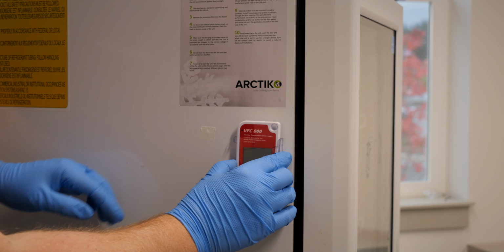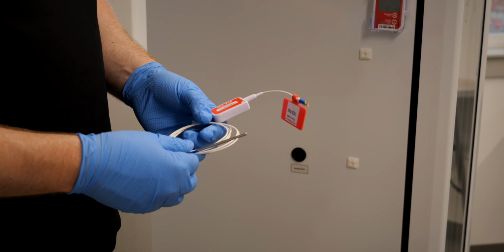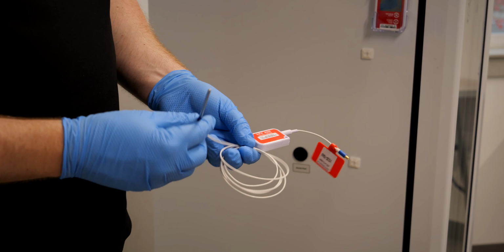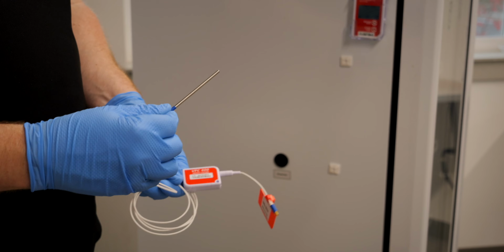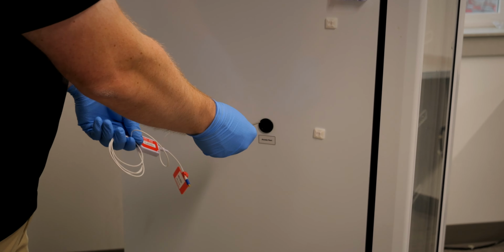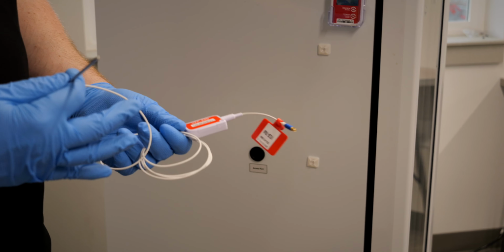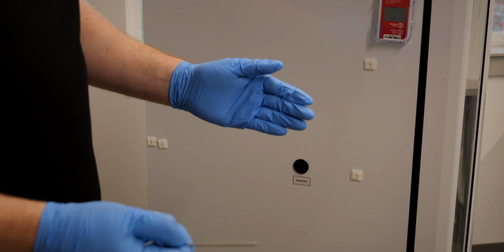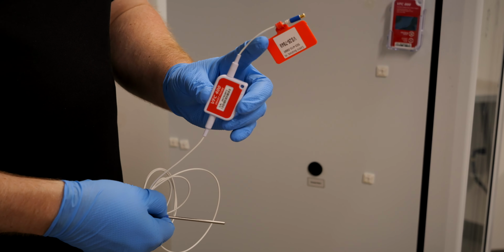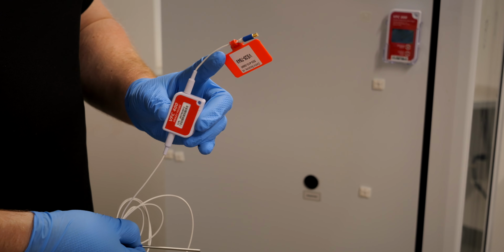Now that we have our data logger and the wall mount bracket placed on the refrigerator, it's time to install and route our probe cable. It is important to note that when installing our temperature probe, we always want to install it probe first into the interior cabinet of the refrigerator. So we're always installing our probe from the outside of the unit into the inside, because this will not fit through most fridge pass-throughs. So that's a tip to make it a little bit easier. That's also why during the unboxing, we took off the cap and seal, and that is to allow us to fit this probe through that pass-through.